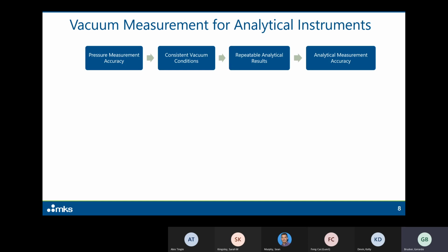If we are going to control vacuum in instruments, you cannot control what you cannot measure, right? One thing that is very true, particularly in analytical instrumentation, is that you need pressure measurement accuracy in order to achieve consistent vacuum conditions in an instrument. Consistent vacuum conditions will provide you repeatable analytical results. And if you have a good calibration curve for that measurement system, that will lead you to accurate analytical measurements. So you can see the connection here.